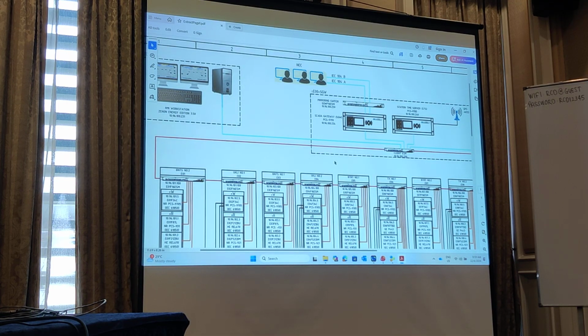If you ask me why, MMS is not actually more stable. MMS consists of more detail, and also Goose has a characteristic where it cannot capture time. So that is the reason, even the real reason NLDC also doesn't monitor the Goose, because Goose doesn't have time quality. Okay? Only MMS has time quality.